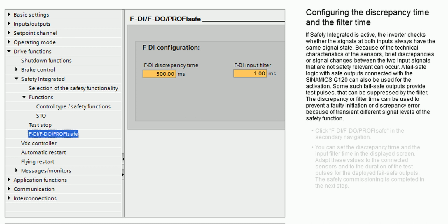If Safety Integrated is active, the inverter checks whether the signals at both inputs always have the same signal state. Because of the technical characteristics of the sensors, brief discrepancies or signal changes between the two input signals that are not safety relevant can occur. A fail-safe logic with safe outputs connected with the SINAMICS G120 can also be used for the activation. Some such fail-safe outputs provide test pulses that can be suppressed by the filter. The discrepancy or filter time can be used to prevent a faulty initiation or discrepancy error because of transient difference signal levels of the safety function.